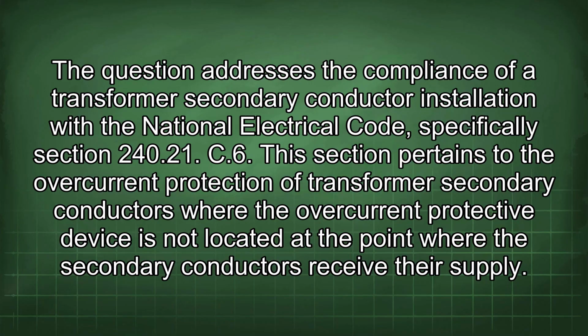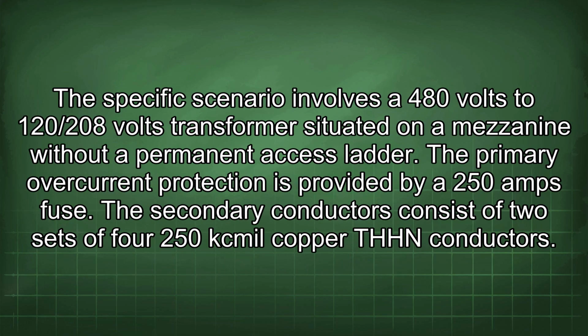The question addresses the compliance of a transformer secondary conductor installation with the National Electrical Code, specifically Section 240.21(C)(6). This section pertains to the overcurrent protection of transformer secondary conductors where the overcurrent protective device is not located at the point where the secondary conductors receive their supply. The specific scenario involves a 480 volts to 120/208 volts transformer situated on a mezzanine without a permanent access ladder.